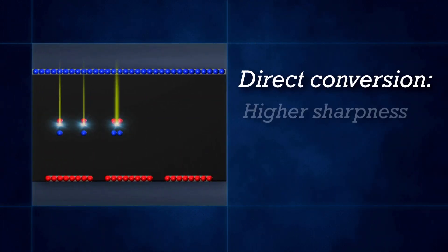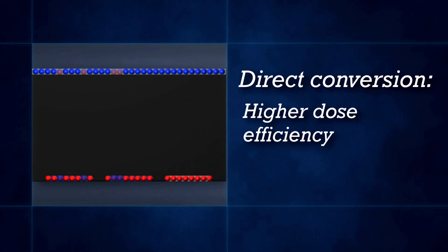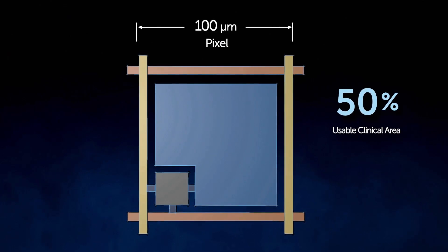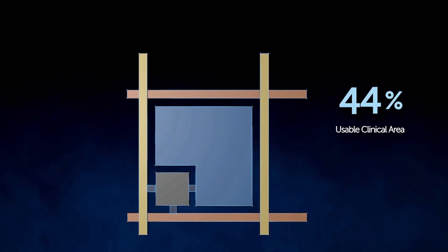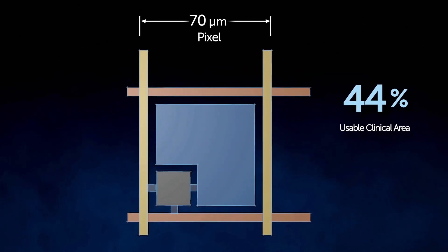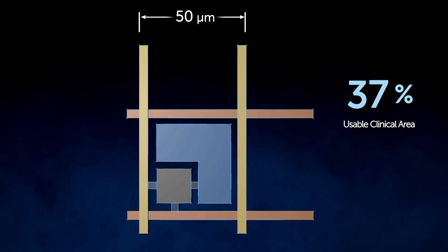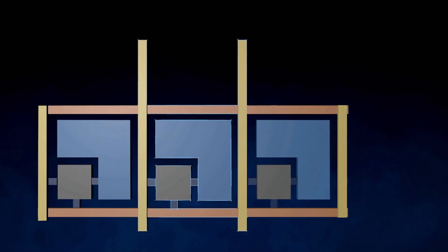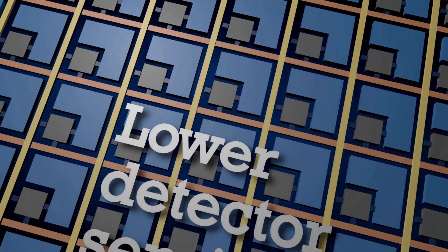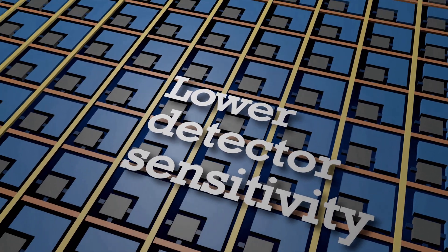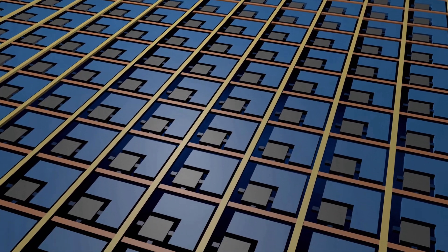Direct conversion increases sharpness and dose efficiency, but there are challenges to reducing pixel size using conventional technology. As pixel size is reduced, the usable clinical area from each pixel is reduced, as more and more space is occupied by electronics such as thin film transistors, resulting in lower detector sensitivity and increased noise.